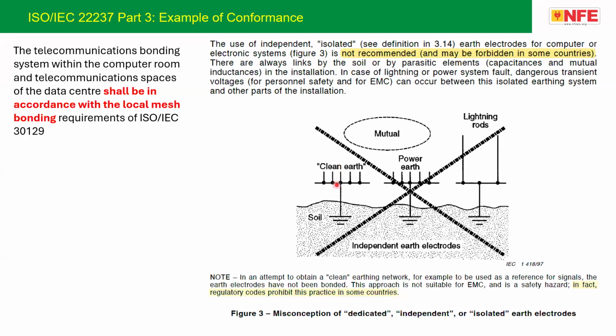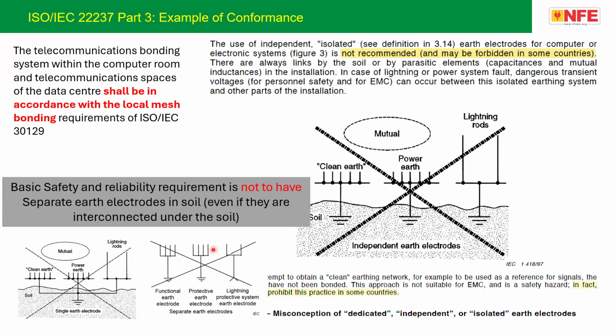61000 explains that putting separate earth electrodes in soil, clean earth, power earth, lightning rod, is not recommended and may be forbidden in some countries. This approach is not suitable for EMC and is a safety hazard. In fact, regulatory codes prohibit this practice in some countries. That means putting a separate earth electrode is a violation of the standard, even if you are interconnecting everything under the soil. Yes, it's a violation.